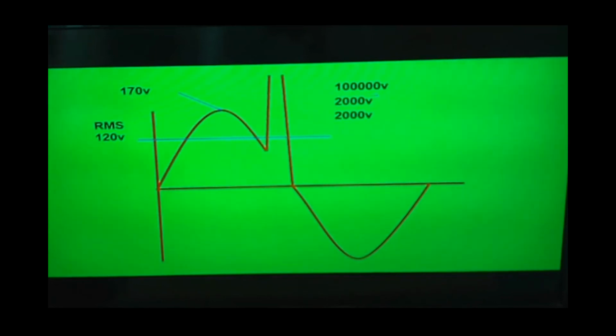Not only do you have transients from lightning, but you have power system switching from utility companies. You've probably seen all these big switching yards around towns and around industrial areas. Those big switching yards are used all the time. All day long, these guys will open up and close air switches. If they need more power in one area and less in the other, they reroute it. And every time they open and close a switch, they create a transient voltage of about 2,000 volts.